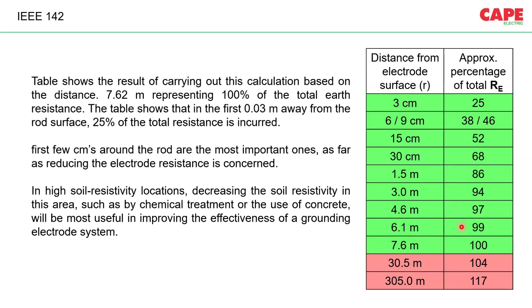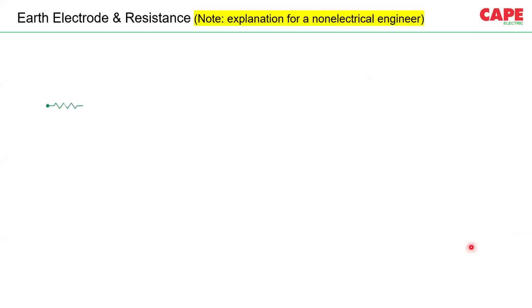Now, in this table, 100% resistance of the earth electrode is achieved at a distance, or the influencing area, of 7.6 meters. 52% of the influencing area is within 15 centimeters. That means from the earth electrode, within 15 centimeters, half a foot, 52% of the voltage gradient has been reduced. Within 30 centimeters, the voltage has reduced to 68%, and at 7.6 meters, about 100% of the resistance is achieved. How can we read it in these cases? Further explanations are there in IEEE 142.